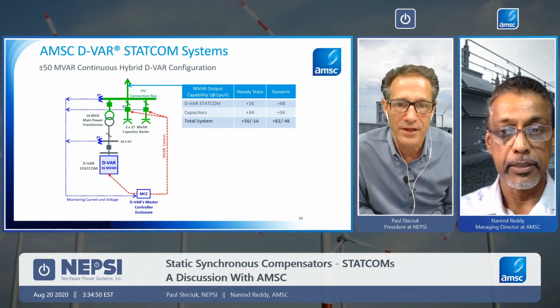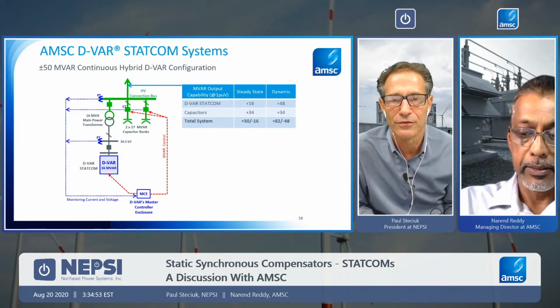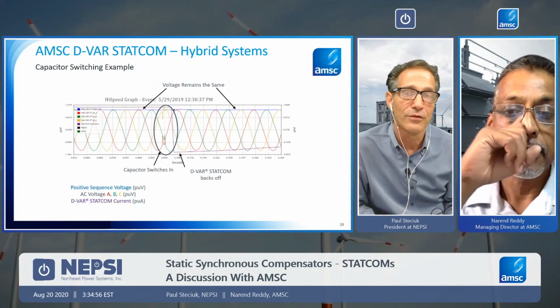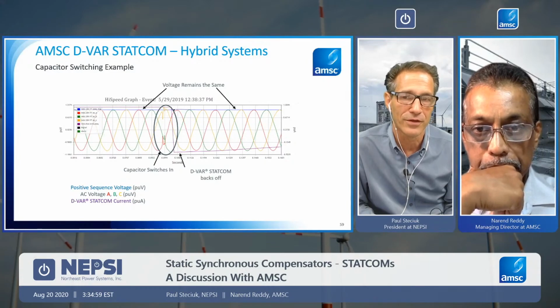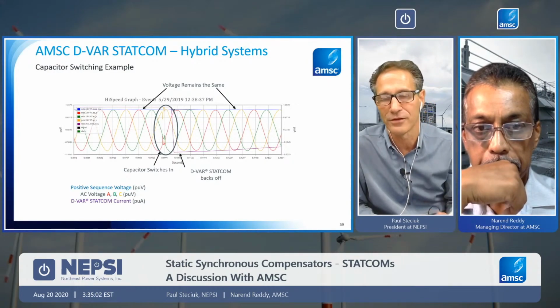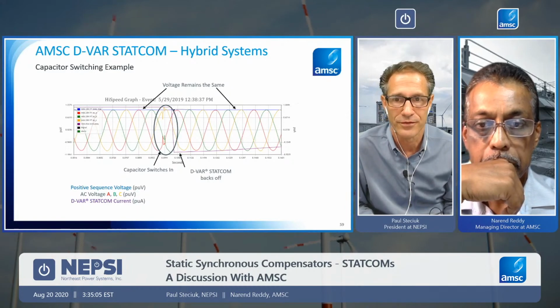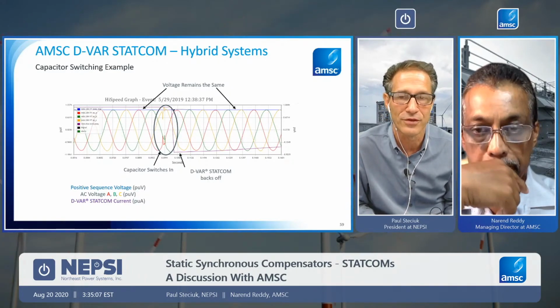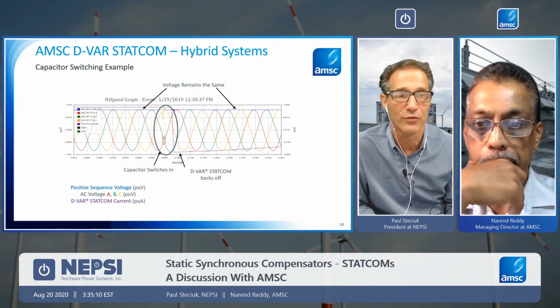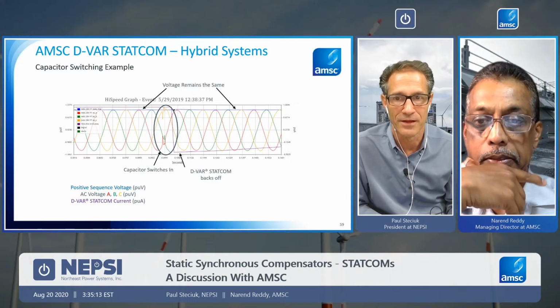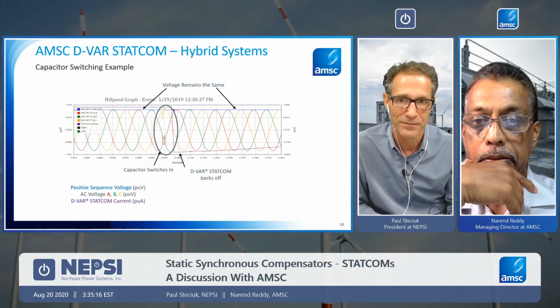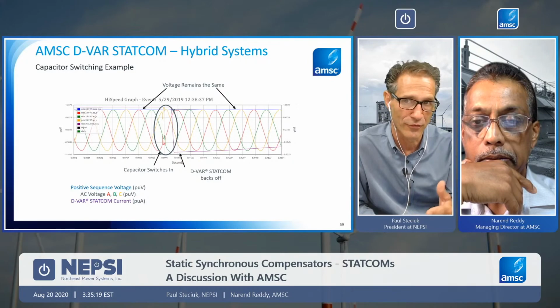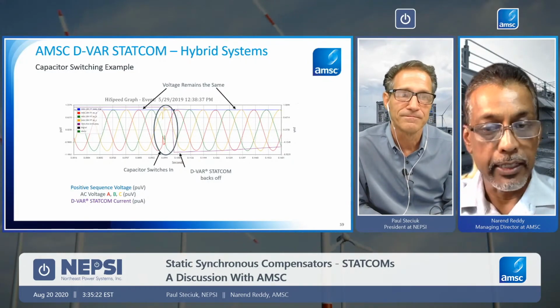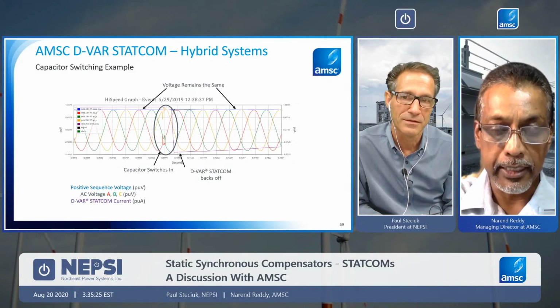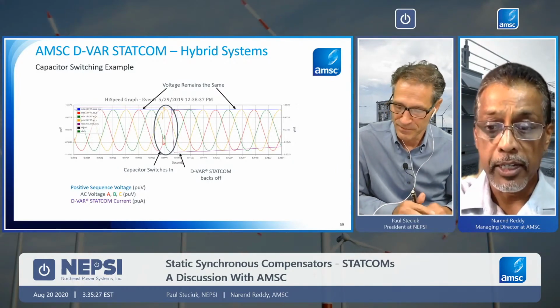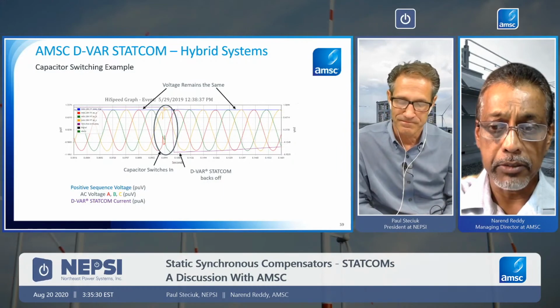Absolutely. Yeah. And then on the next slide, 59, you show a transient. So especially at the 38 kV level, but even at the 15 kV level, the transients can be eliminated with the switching device, either a pre-insertion resistor in the switching device or synchronous closing using zero voltage closing. So in that situation, you would be transient free, and that would be a perfect waveform then. Absolutely, yes. There are different ways of addressing that, and you guys are experts on the right devices to do that.